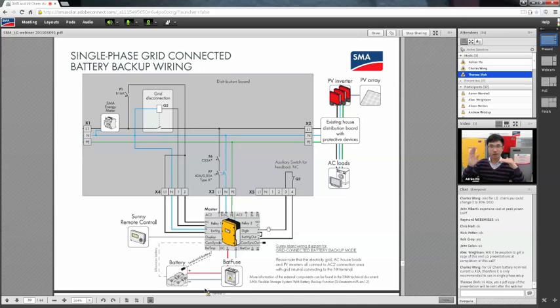Q2 is no longer energized by the grid, so it's going to open. It's normally open. That will result in the auxiliary switch closing, giving the signal to the Sunny Island that it now has 48 volts across. Once the Sunny Island ensures that Q2 is open and there's 48 volts coming through, this will guarantee we are off the grid.